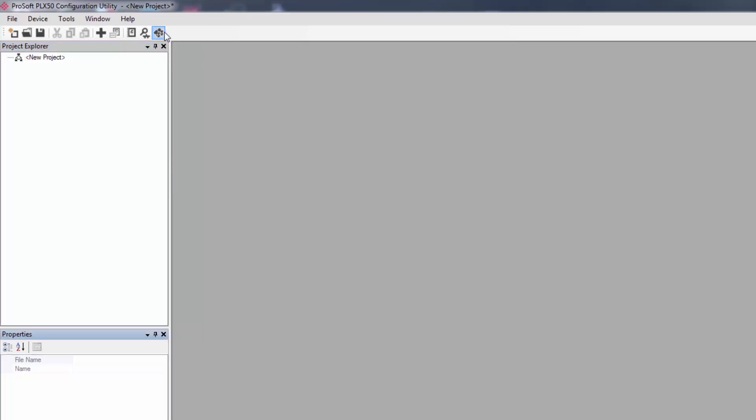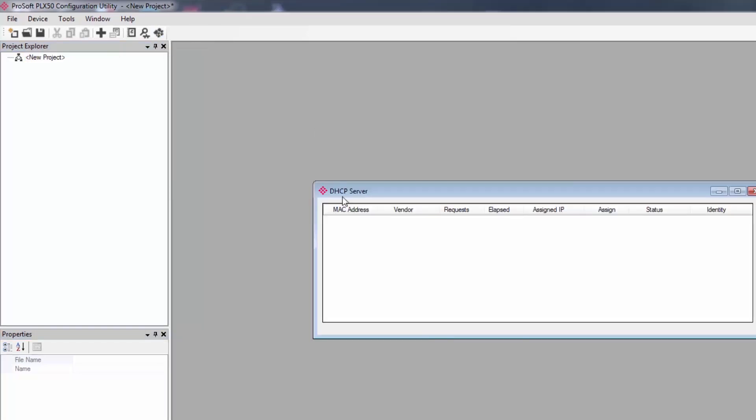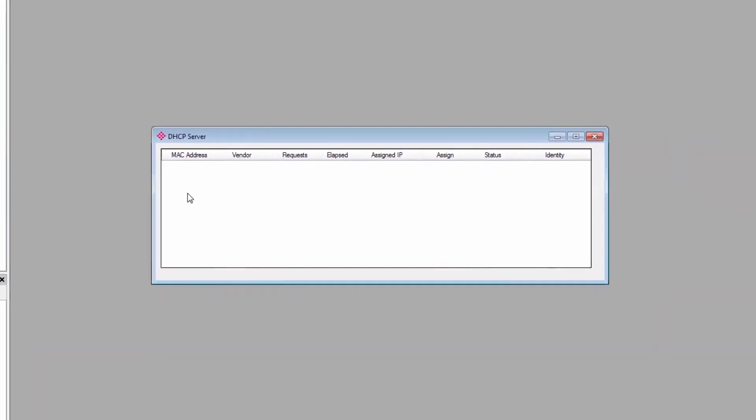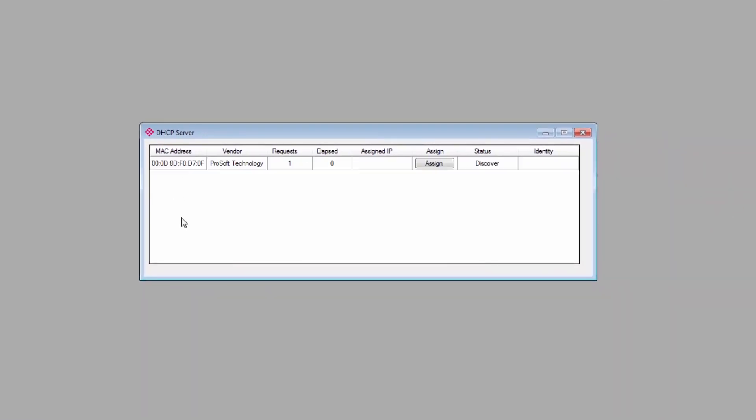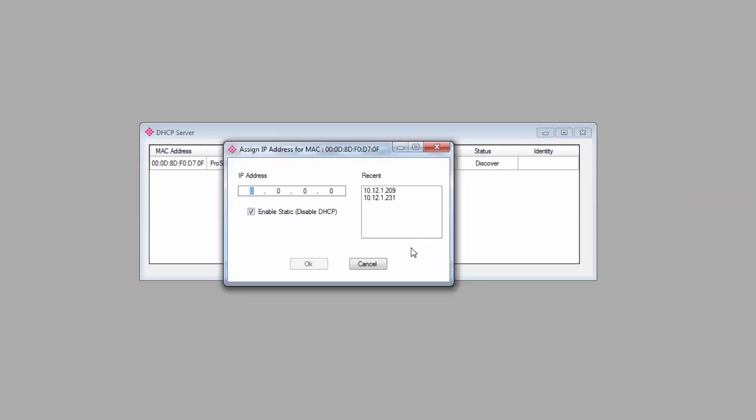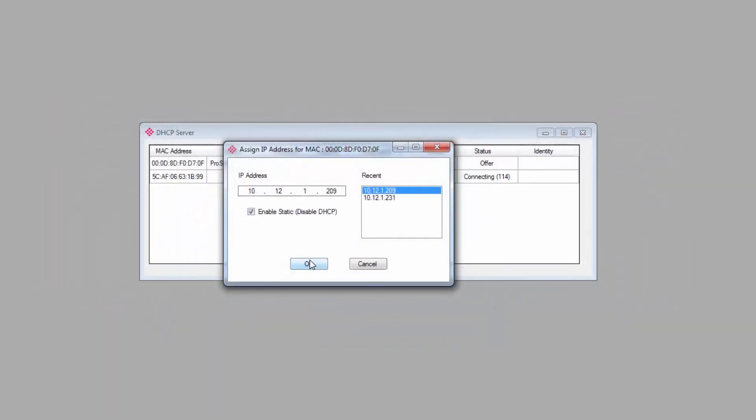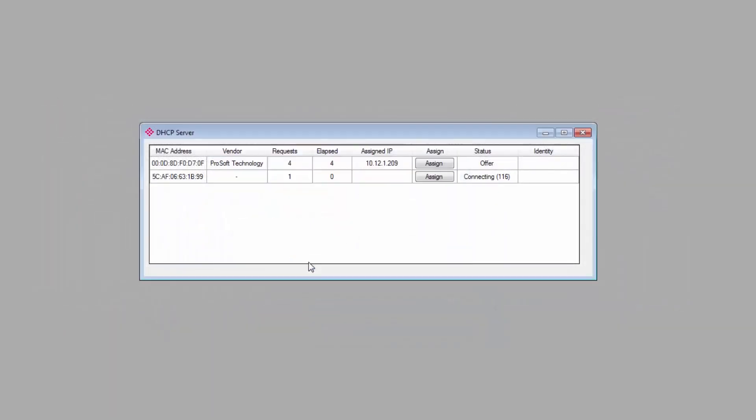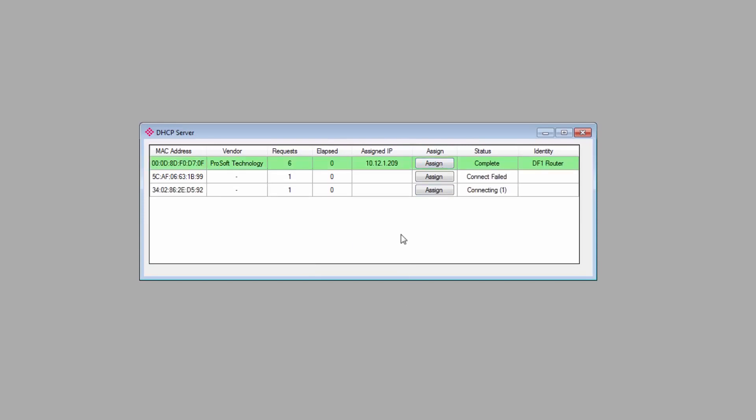The first time you connect the PLX51 to your network, you'll need to launch the DHCP server and assign it an IP address on your subnet. It's this button here in the menu bar, and there is our gateway. Click assign, and on the window that opens, I'll enter in an IP address that I know is available on the local network and click OK. The bar should turn green. This lets you know that the gateway has accepted the IP address and is now connected, so we can close this window.